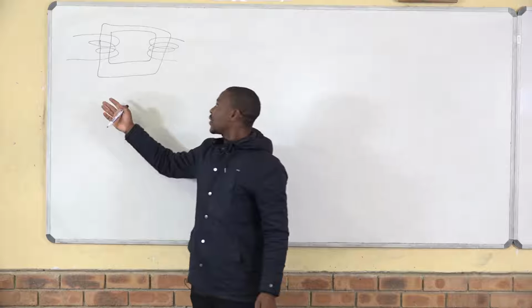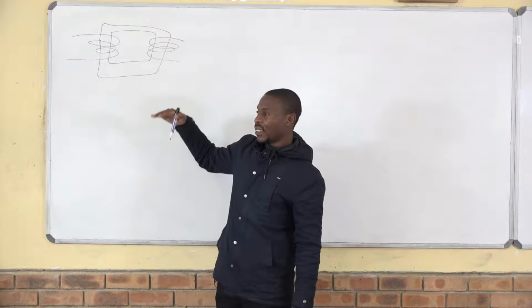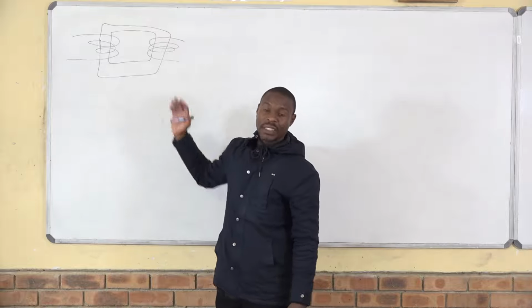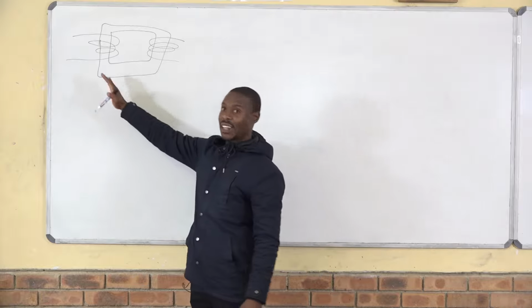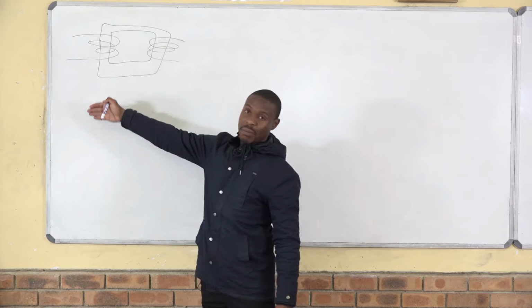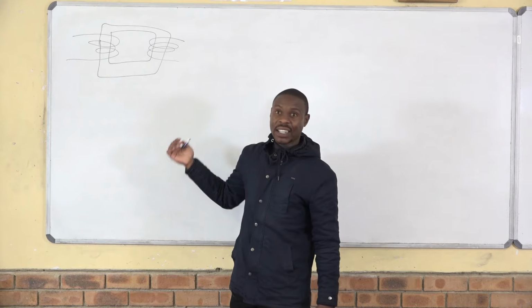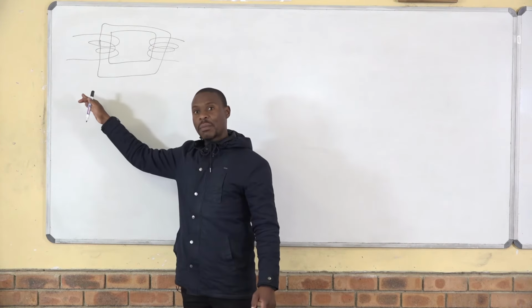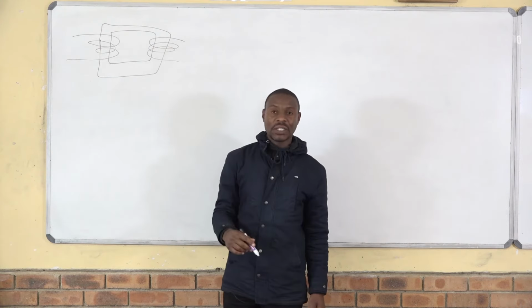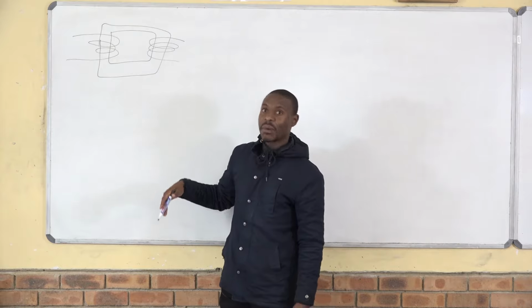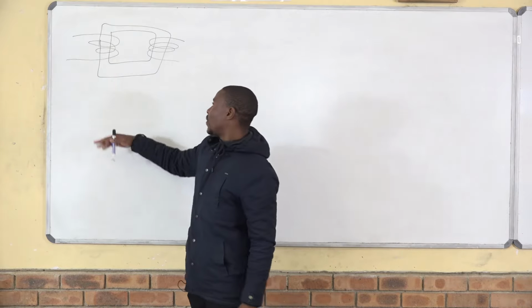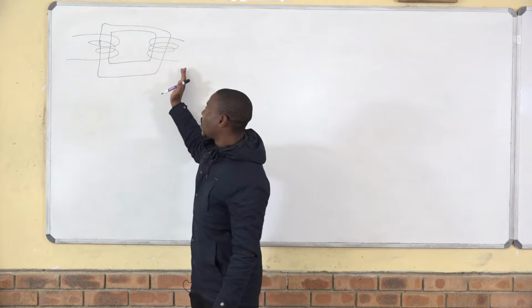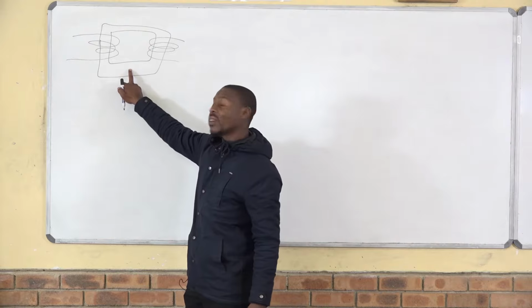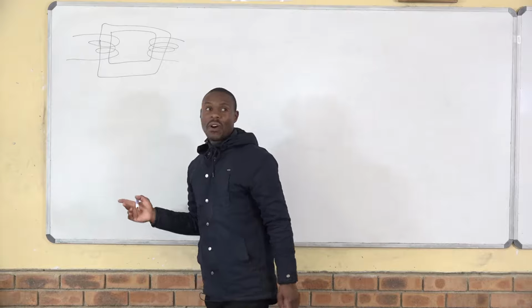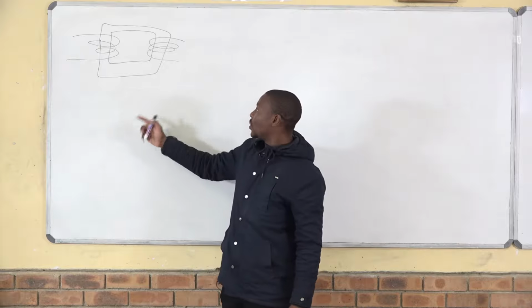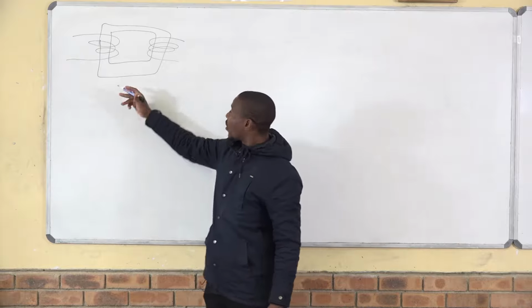And then in these transformers, what you will notice, you will have a step-up or a step-down transformer. What will tell are the number of turns on the primary side or on the secondary side. If you have more on the primary side than the secondary side, then you must know that this is your step-down transformer, vice versa. So we've said this is the primary winding, this is the secondary winding, this is the transformer core. So you have 2 types of core where they can laminate, where they can put your windings.